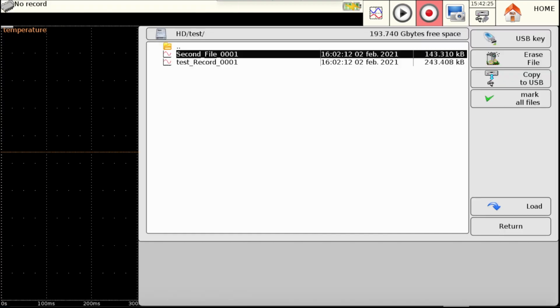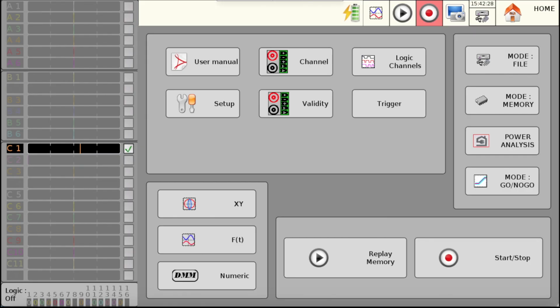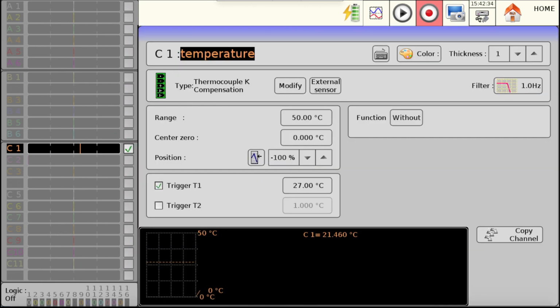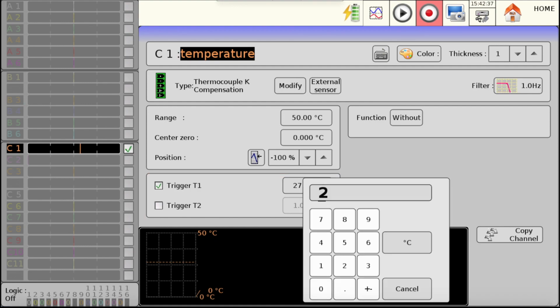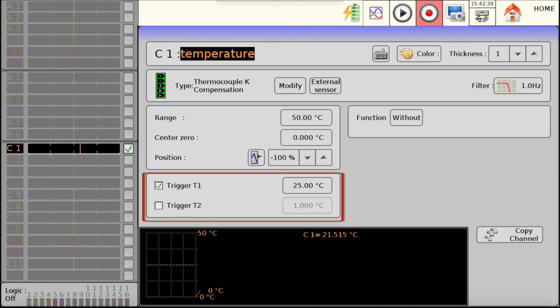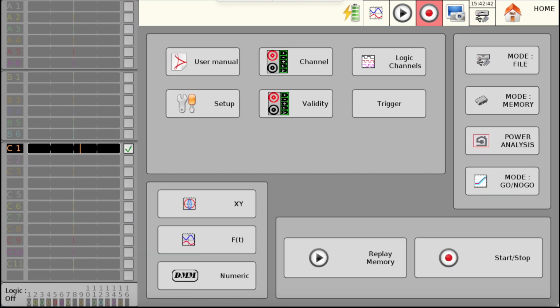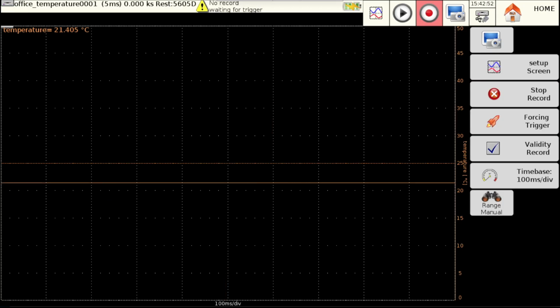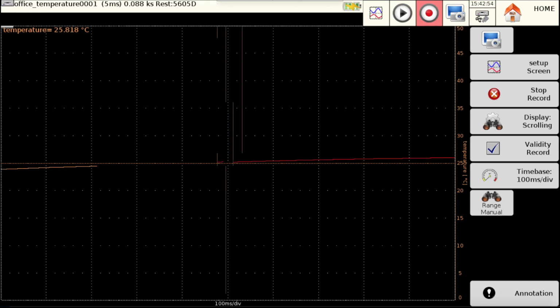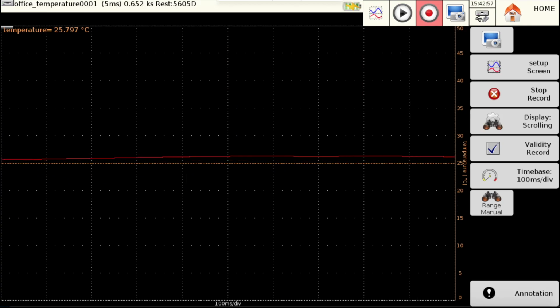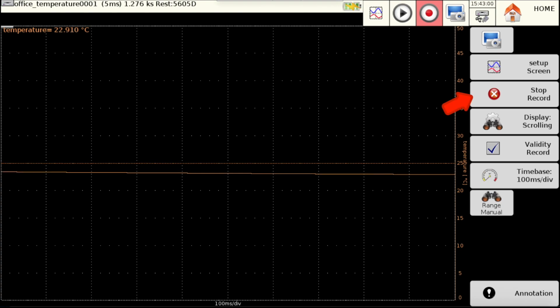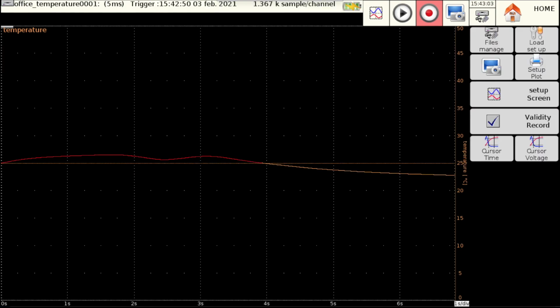We stop the acquisition, go back to the main menu, go to the channel configuration, and lower the value of our threshold to 25 degrees, for example. Go back to the Start-Stop page via the button at the top right of the screen, and let's test our temperature recording again. We can stop the recording. We can see that there was a trigger and that our signal above the threshold is indeed of a different color.